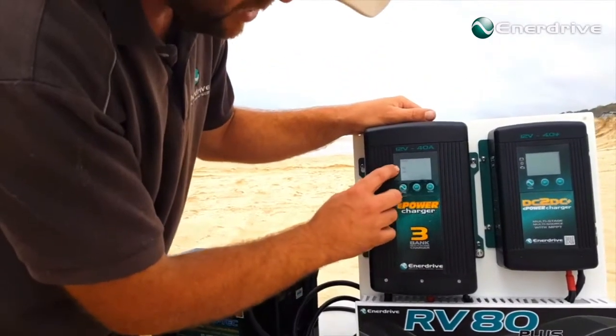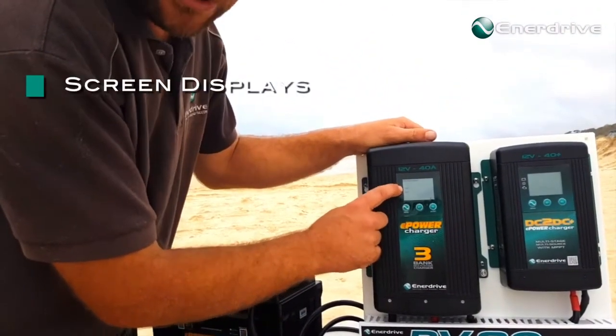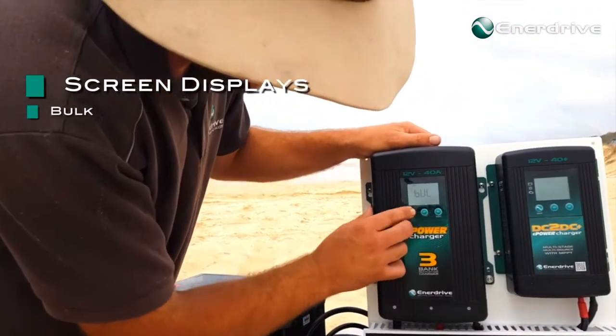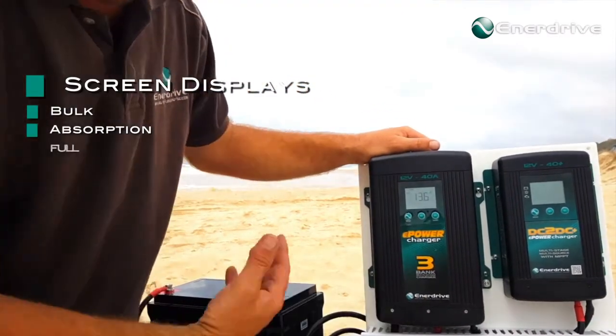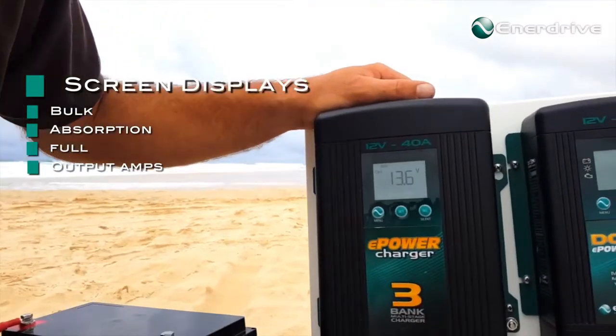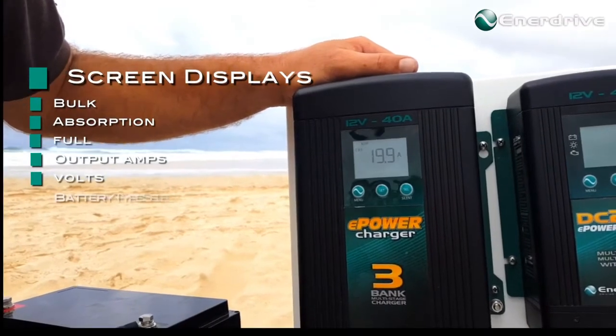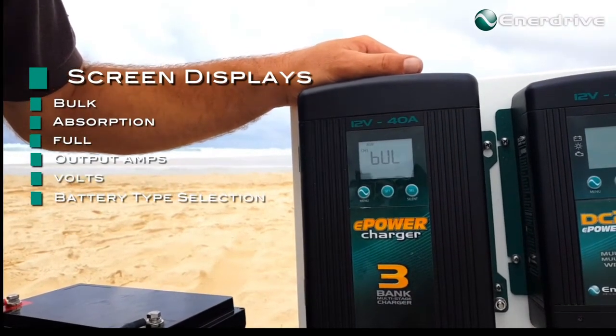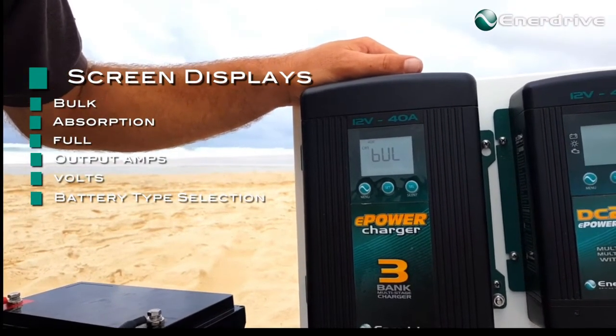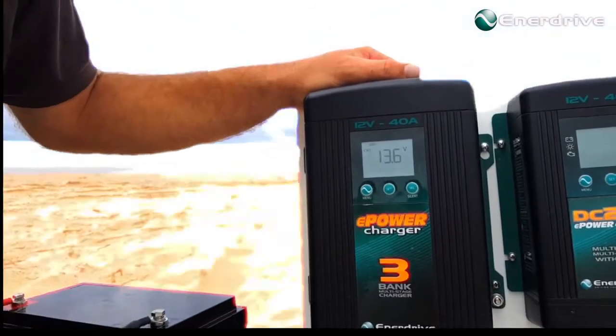Now the other thing you can do here is go through and set up channel 2 and channel 3. We don't need to do that today, but you get the idea. We're back to our normal window, showing us voltage in the system. We're putting in 19.9 amps, remembering I set it to 20 amps, so we're there. And it's showing us that at the moment we're bulk charging.